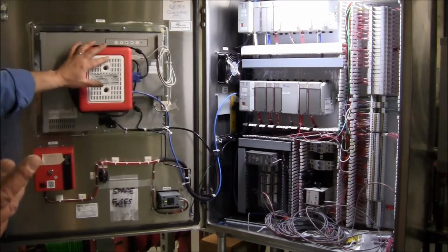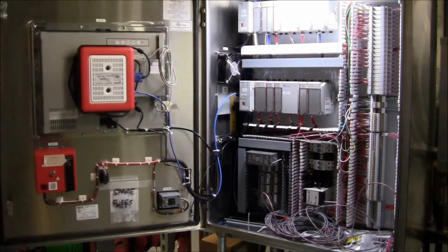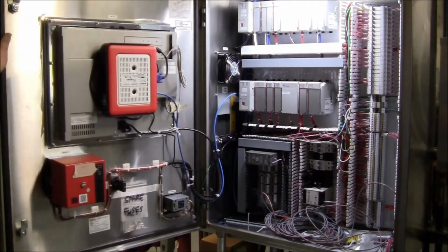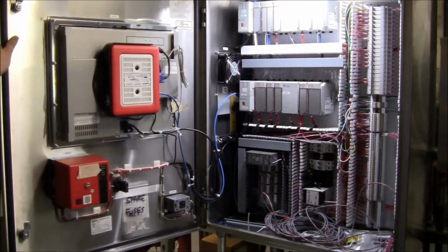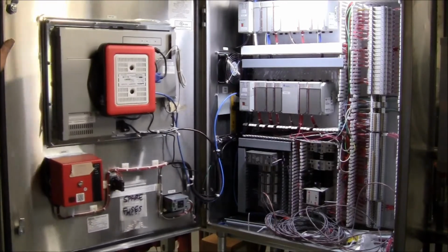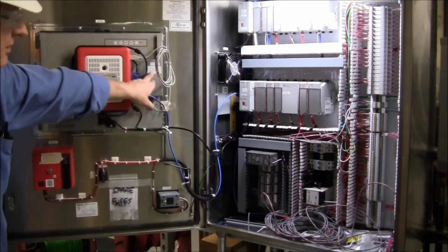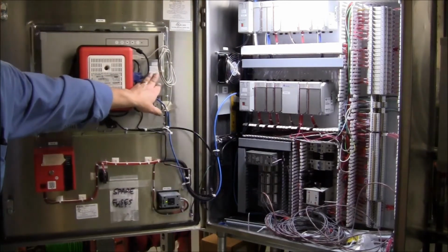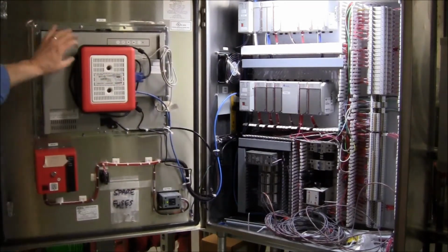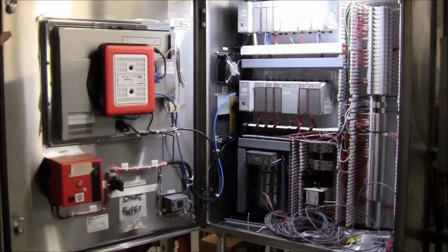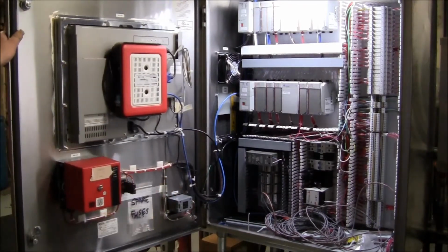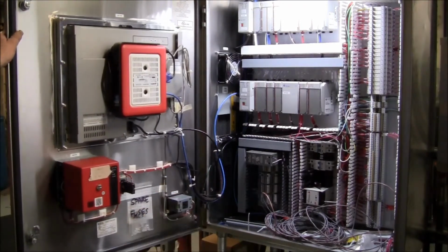When the Arista boots up, it has a very simple operating system that says, hey, I'm a thin client, where's my Thin Manager, and what do I do from there? So the thin client then goes to the Thin Manager, whose IP addresses are listed here, and the Thin Manager server says, oh, you're this machine on boiler 1, you get these screens, you do this, away you go.